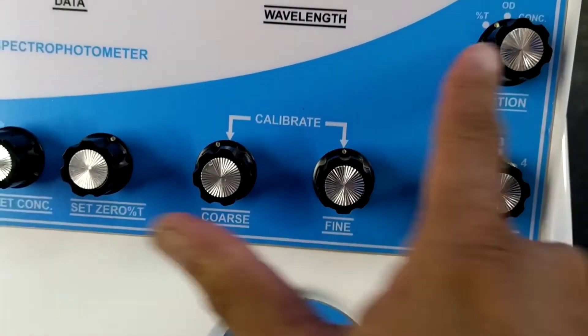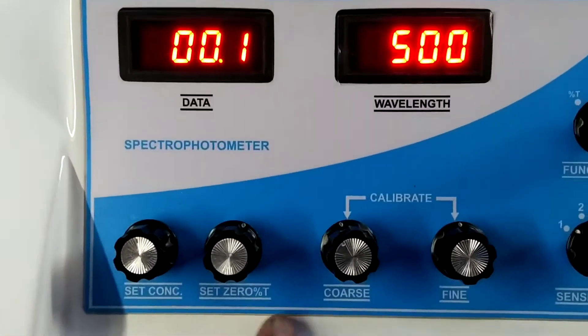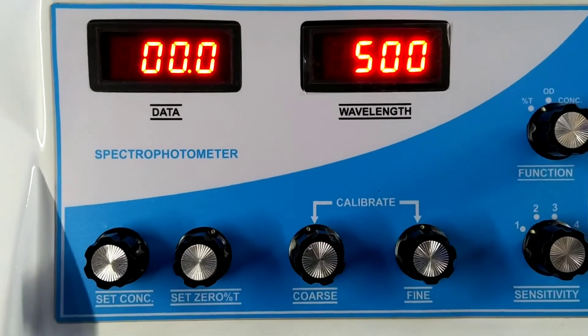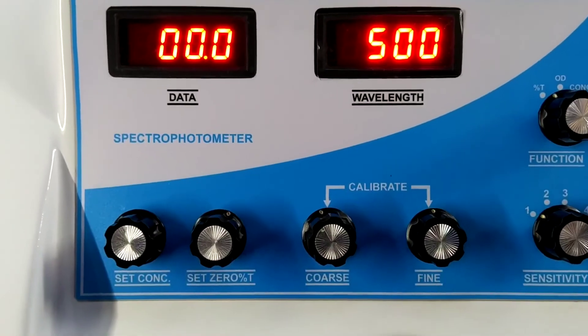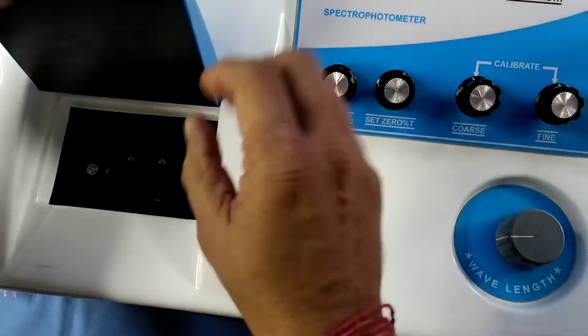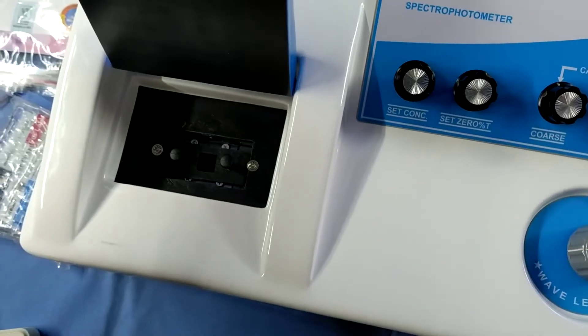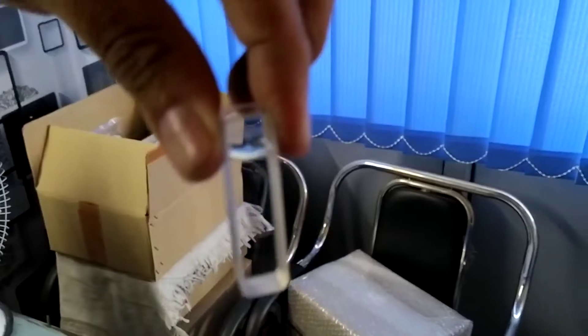Now, on percentage T, you set preset zero from the 'set zero percentage T' control. This is the preset zero, so on 500 nm, I am now placing the blank. I am using distilled water as the blank. This is the glass cuvette.